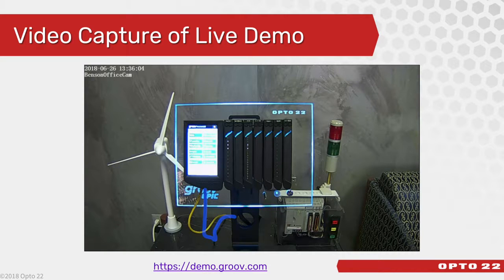The blue cable here is to my isolated OT control network, where you can see I have an Allen Bradley Compact Logix PLC which is wired up to this stack light. Then the EPIC itself is mounted on an 8-module chassis with various I/O modules to control the turbine's on-off state, its speed, temperatures, and various other I/O.